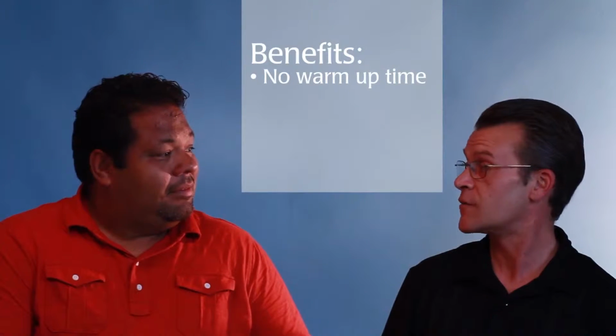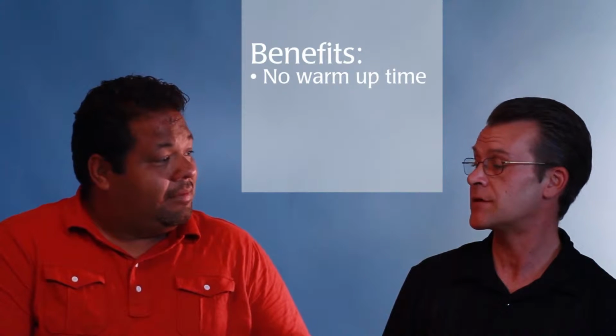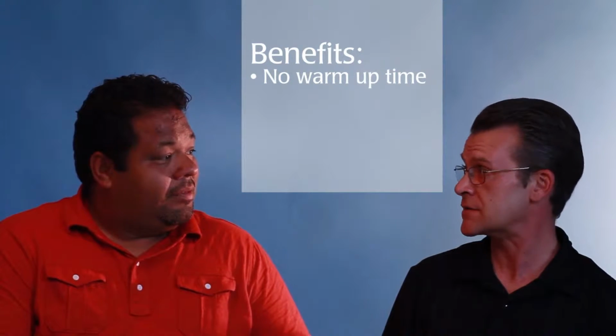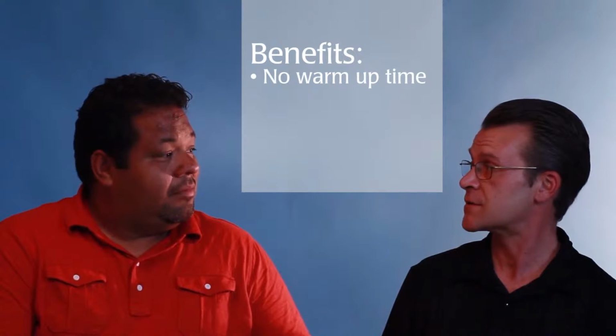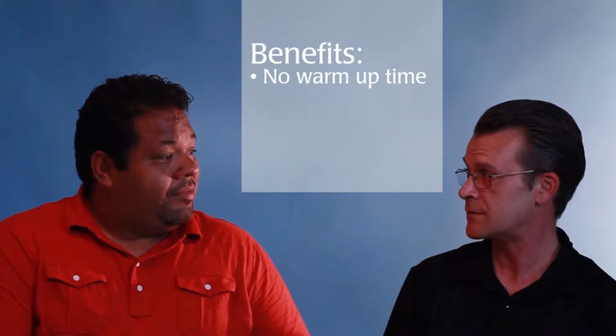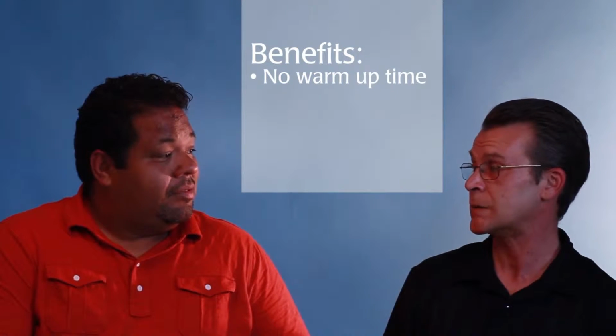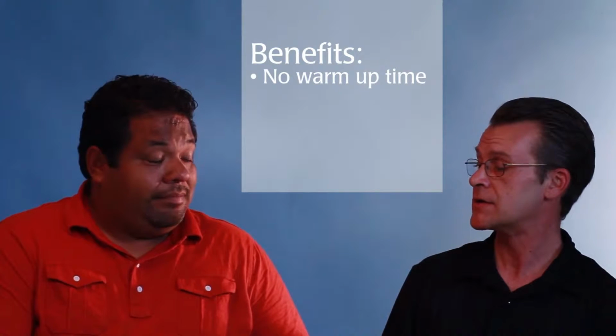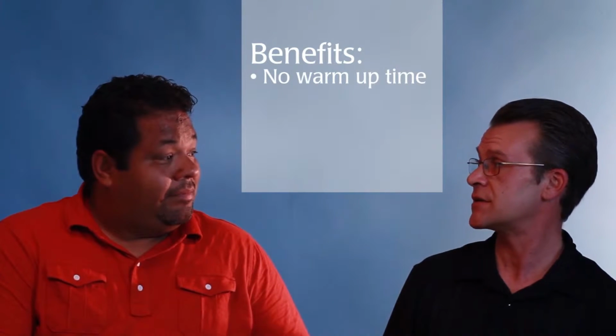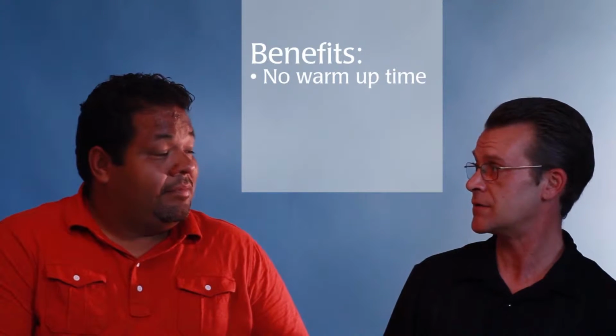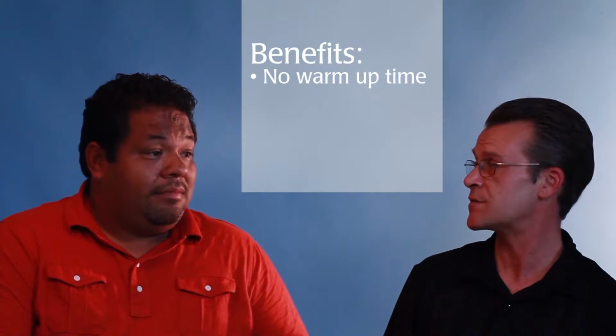What are some of the benefits of the BF 100? Firstly, there is no warm-up time with this instrument. The BF 100 uses LED technology. A traditional light source uses a mercury vapor or halogen lamp, which requires anywhere between 20 minutes and 1 hour of warm-up time. Since this does use LED technology, it actually has no warm-up time. You can turn the instrument on and begin your experiment right then.